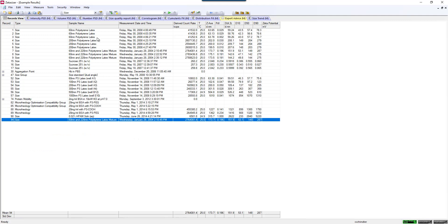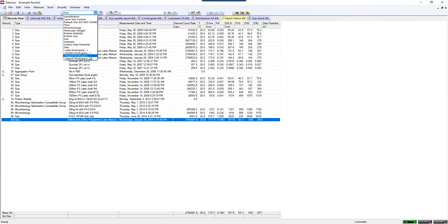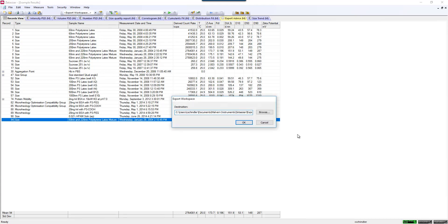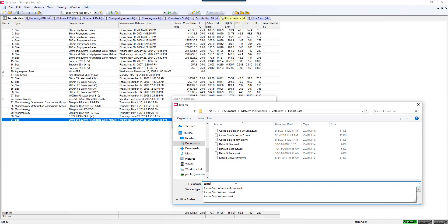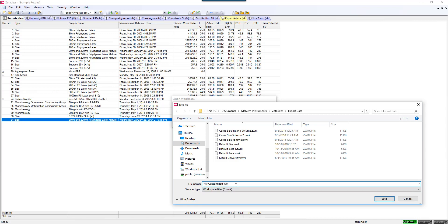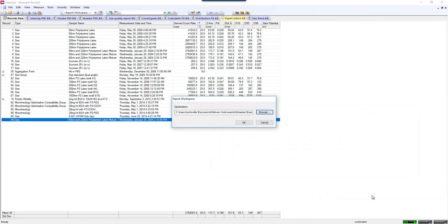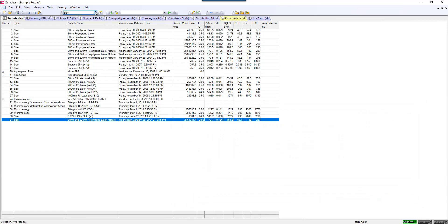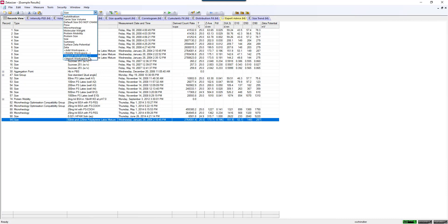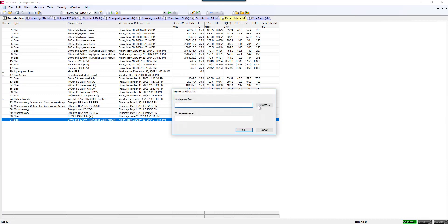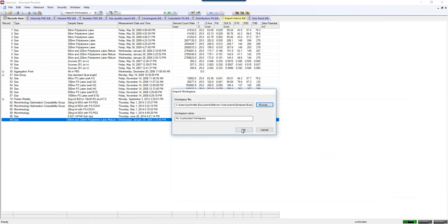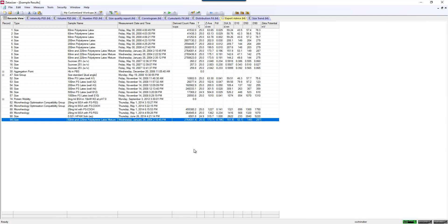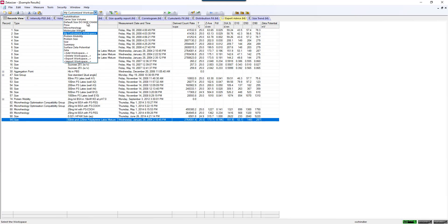At this point, I would probably go in and save this workspace. I would save that just as we did before, export workspace. Make sure that you're saving that in a place that you know. Maybe I could call this my customize workspace. You probably give it your names since you have a lot of other people using your instrument. Save that, and then import that back into your workspace queue. Or if you did this on the computer with the instrument, and let's say you wanted to go off on your own computer and you wanted that exact same workspace, you go take that workspace, put it onto your computer, and just import it into your workspace.